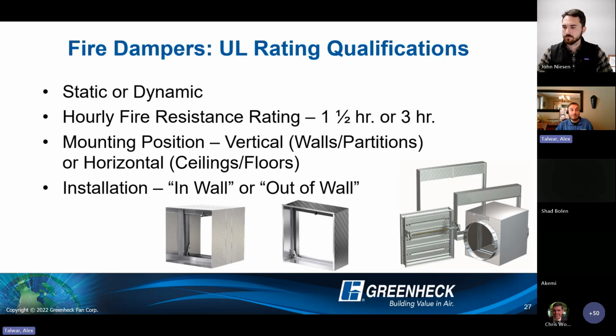Mounting position is also important. So, if this product is going vertical mount in a wall or horizontal mount in a floor or ceiling, again, if it is going in the ceiling, make sure you actually need a fire damper, not a ceiling radiation damper. There are differences in how these products are manufactured based on if they are vertical or horizontal, so that is important to know up front. They're not universal mounting. And then, in wall or out of wall in terms of installation.